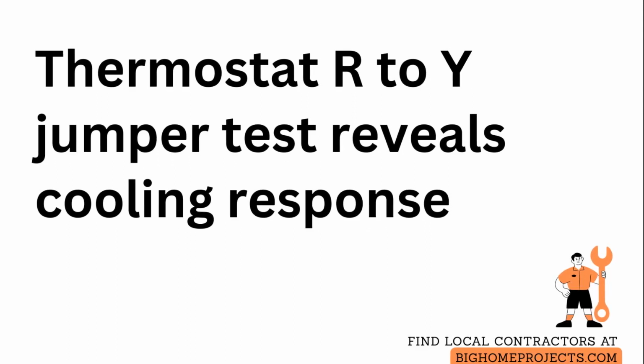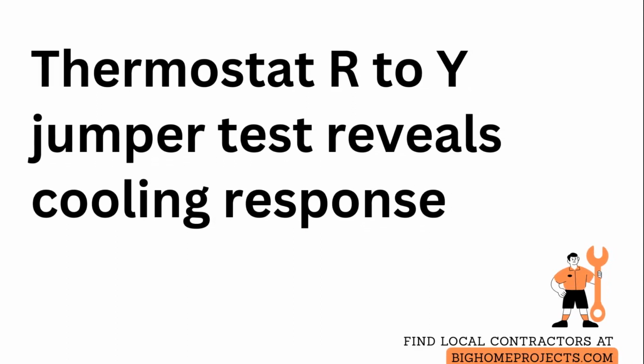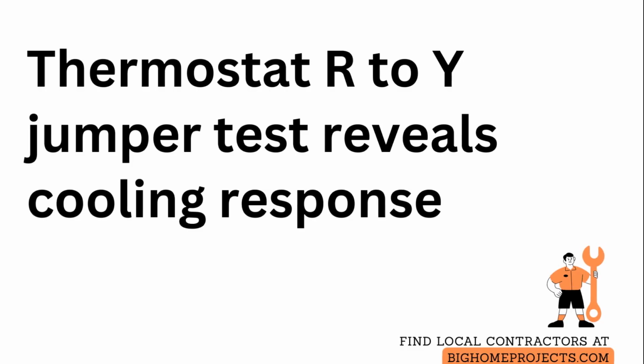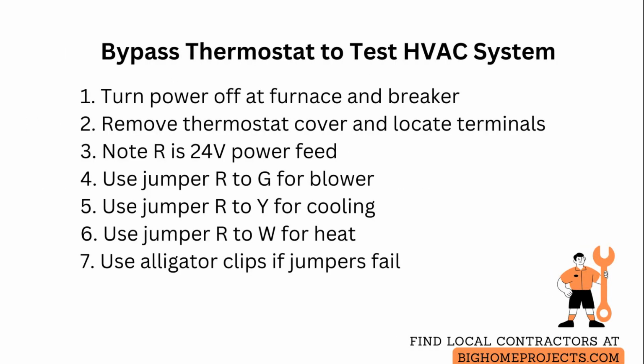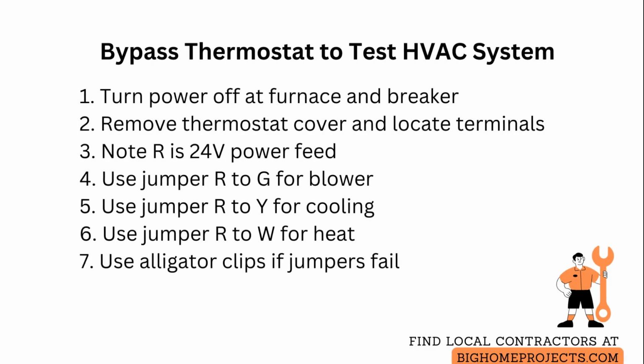To test whether the thermostat is the problem, bypass it by directly connecting the system control wires at the thermostat base. Start by turning the power off at the furnace or air handler switch and at the circuit breaker to remove any risk of shock or short.